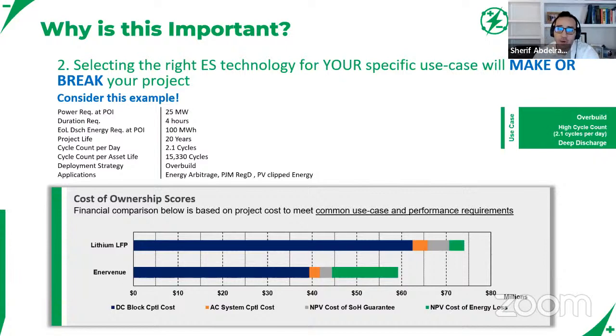The main question was: we know this nickel hydrogen battery is really good at degradation. It's rated for 30,000 cycles and guaranteed for 20,000 cycles. As it executes these cycles, it doesn't degrade as quickly as lithium. But on the other hand, it's not as efficient as lithium.